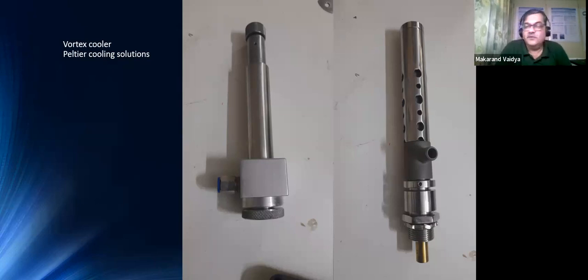There are various techniques; the simple one is dilution, where you purge the control panel. But if something goes beyond that ambient condition, you have to cool it down, so for cooling you require AC. There are explosion-proof air conditioners available, but they are very costly. Sometimes simple techniques can also be used, so we developed this vortex cooler, and now we are going to make models and a typical catalog for different sizes of BTUs and so on.